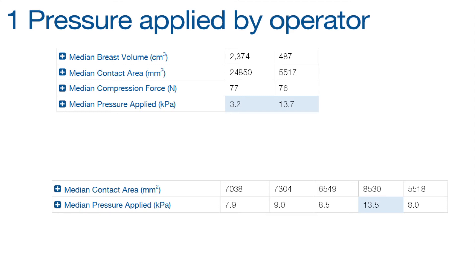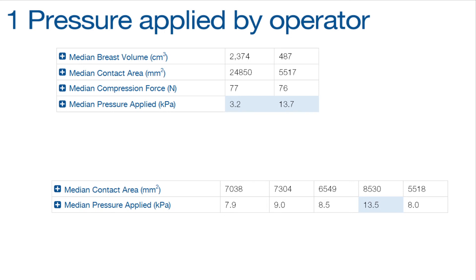In both cases, Volpara Analytics provided objective evidence to confirm an issue and take corrective action. In another example, Volpara Analytics was used to identify that the default configuration settings for a certain mammography unit differed from the others and needed to be adjusted to standardise screening. This simple correction led to reduced variability in patient experience and image quality.